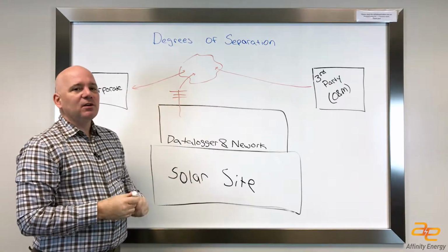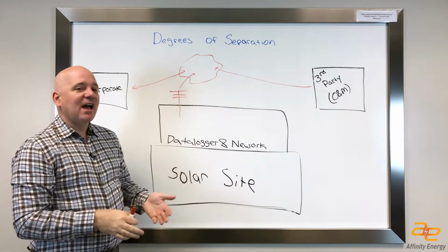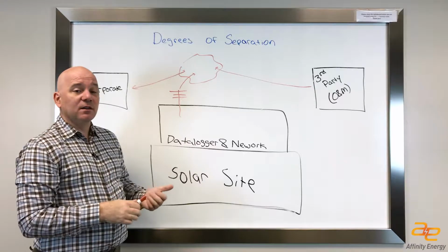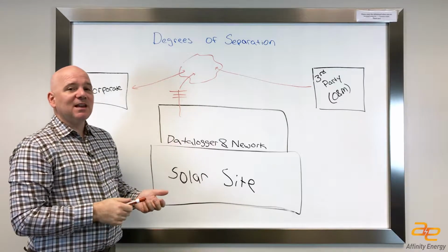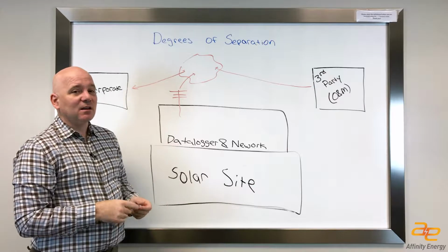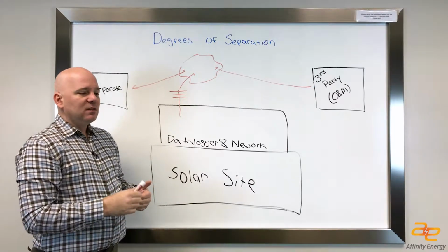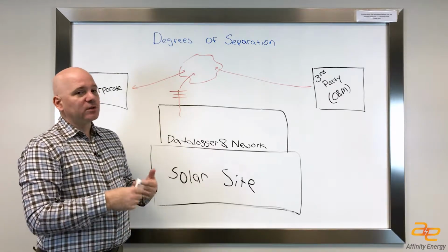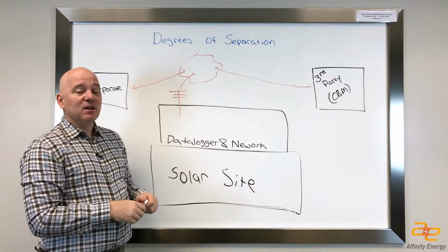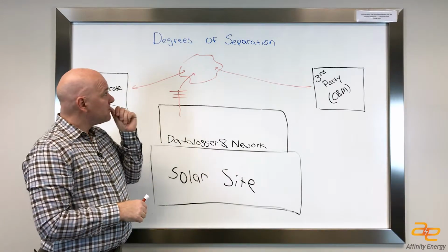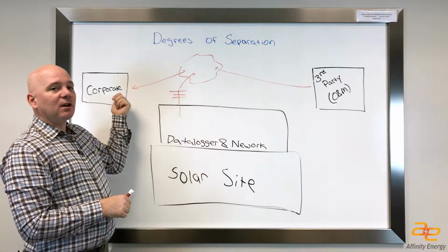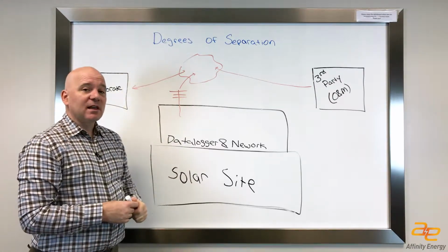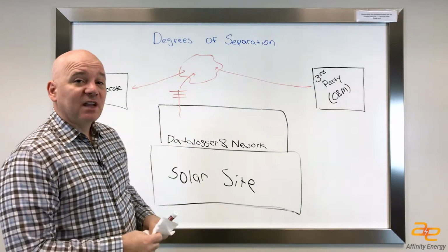these cloud apps typically only give you 1-minute at best or 5-minute data. It might even be 15-minute data for the status of the devices that are running at the site. And with 15-minute data, and even with 1-minute data, you really can't see how the individual inverters are performing through clouds or changes in voltage or any of the events that happen at the site. You lose a lot of resolution in the data. So corporate is looking for much higher fidelity data. They want 1-second data from the site. And going through a third-party cloud app just doesn't seem to work for these kinds of applications.